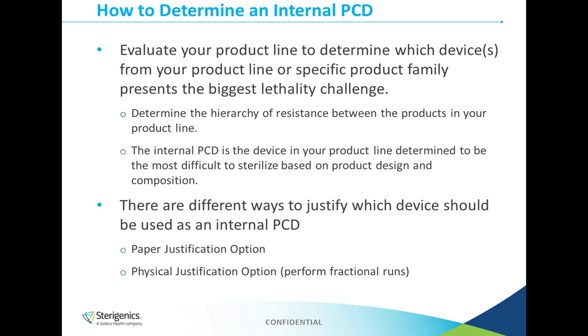Now, how do you determine which is going to be your internal PCD? You're going to evaluate your product line to determine which device from that product line or from a specific product family represents the biggest lethality challenge. To do this, you're going to determine the hierarchy of resistance between the products in your product line. And this internal PCD is the device that you determine to be the most difficult to sterilize based on the product design and composition. Now, there's a couple of different ways that you can go about determining which device is going to be your internal PCD.